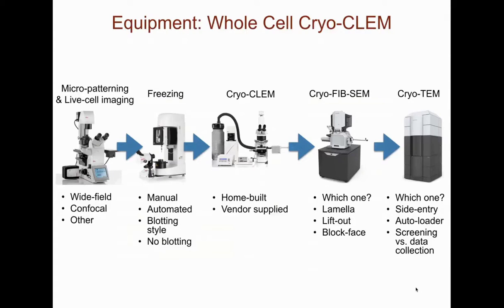We are all investigating exciting biological questions that may benefit from light and electron microscopy imaging. However, we may not know what resources we need or whether we should house them in our own laboratories or use shared resources. For the ideal and highly automated cryo-CLEM workflow, one will need access to live cell imaging systems, a plunge freezer, a cryo-CLEM microscope, a cryo-FIB system for sample thinning, and a cryo-TEM.